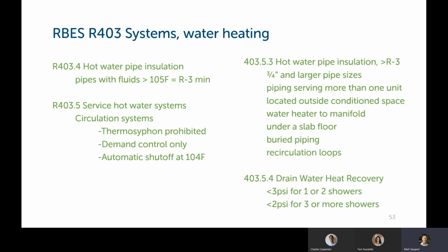Hot water pipe insulation is required on pipes 3/4 inches and larger. Pipes that serve more than one unit or located outside conditioned space. It's required between the water heater and a manifold. It's required under a slab floor, buried piping, for instance, buried in attic insulation, and on recirculating loops.